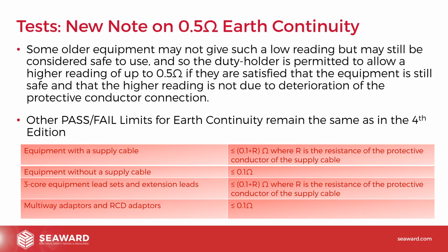What we have actually done on the Apollos, we've put new test sequences that we're preparing for the 5th edition Apollo firmware update, and in there we have put a 0.5 ohm test sequence just to cover this. And obviously, if you're doing your own test sequences, you can include those, and you can write your own sequences to allow for that. But we're just making you aware that it is in there, but it's not a major change. This is just recognising there was some older equipment that wouldn't comply with 0.1 plus R, because of the standards it was designed to, but we are talking a tiny amount of very old equipment that would fall into that category. And obviously using the 0.1 plus R is always on the safer side anyway, really. So I would imagine most duty holders will still just go with the 0.1 plus R and not the 0.5 ohm option.